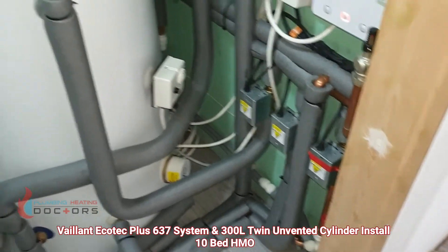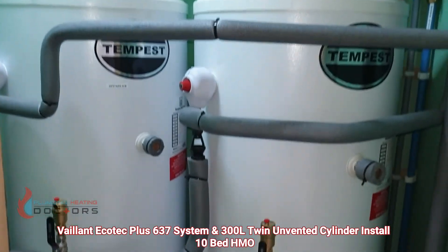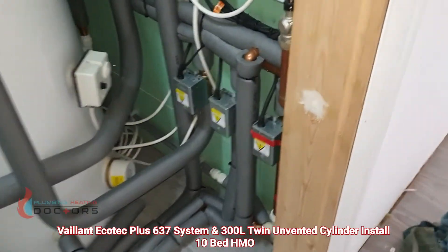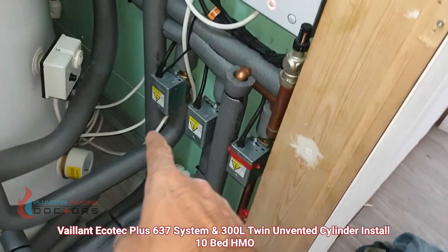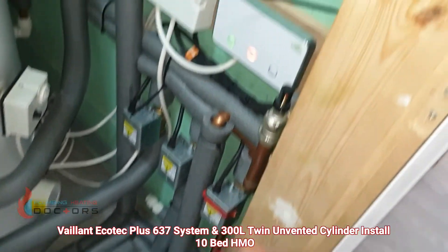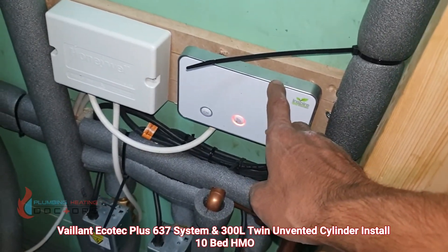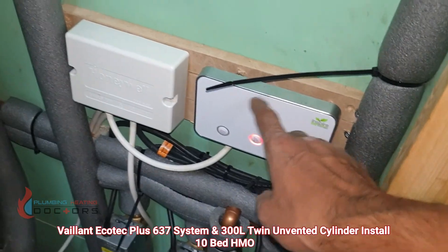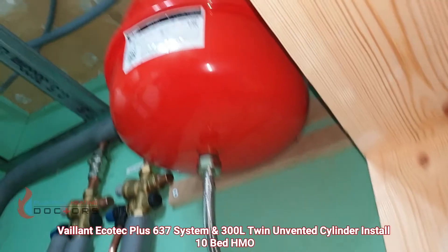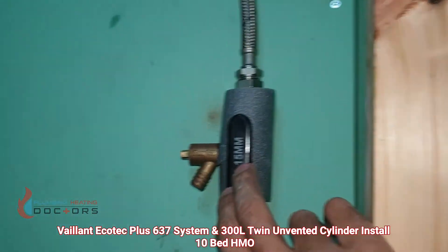Two 300-litre unvented cylinders in here, indirect. We've got 3-port valves there — one, two, three — two for the hot water, one for the heating circuit, bypass, wireless heating control, landlord-specific one called Inspire. We've got a filling loop there, an expansion vessel for the heating side, and an isolation valve for maintenance use.